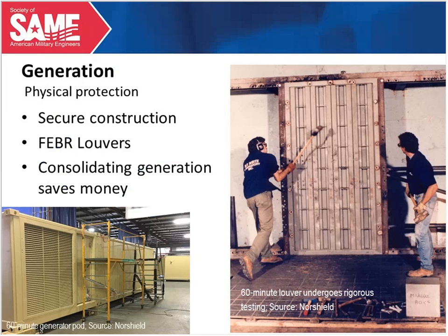One more thing on generation: if you've got a high threat facility, and more installations are being considered high threat even stateside, you really need to protect your generation and your fuel, but especially your generators. That can be difficult because generators need a lot of air, for combustion and for cooling. To move that much air to them, you typically need very large air openings, which presents a problem if you want to secure those generators. So you typically have to protect your openings, and the biggest openings need to be protected by hardened louvers.